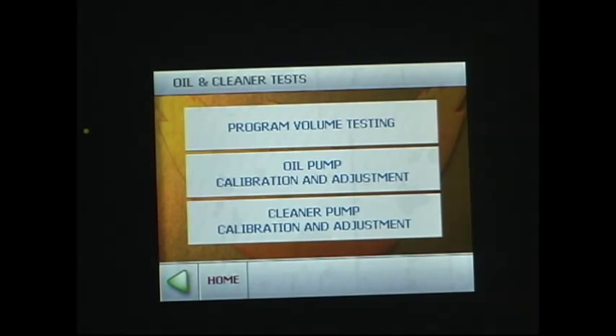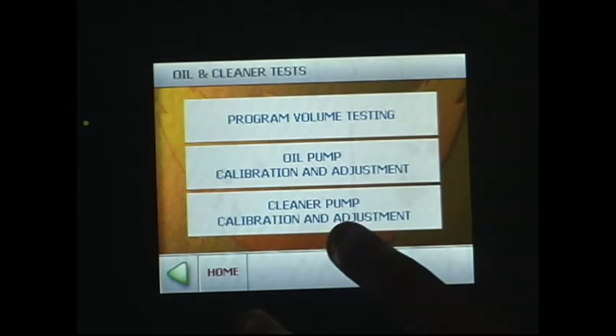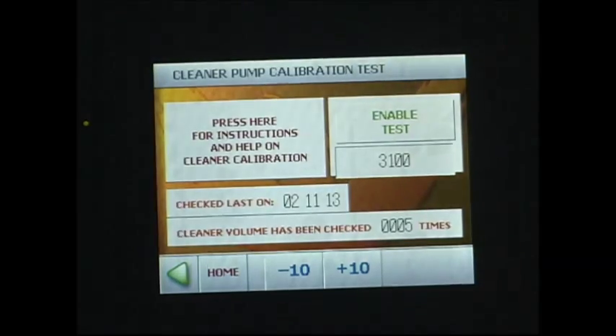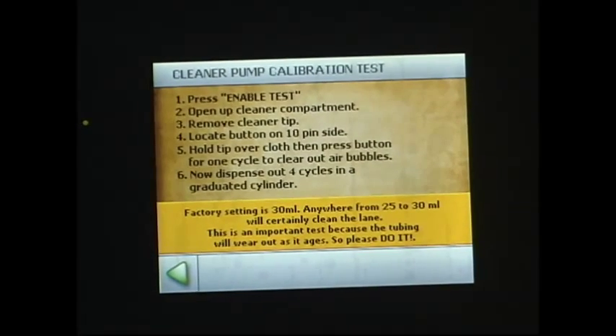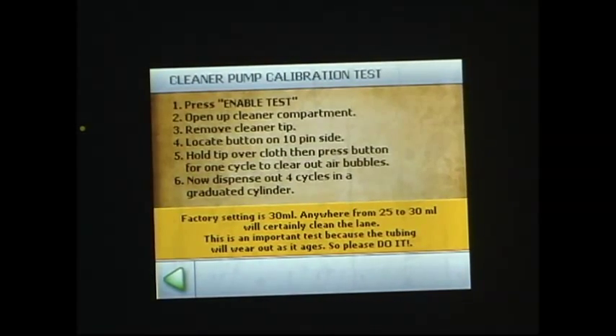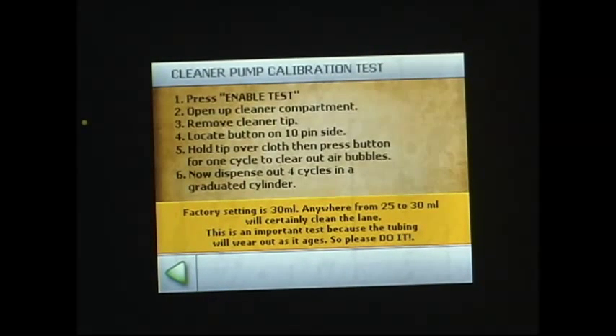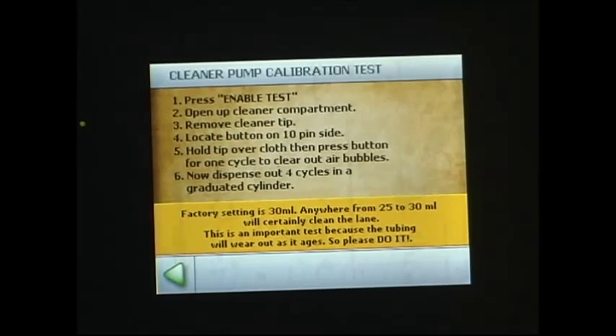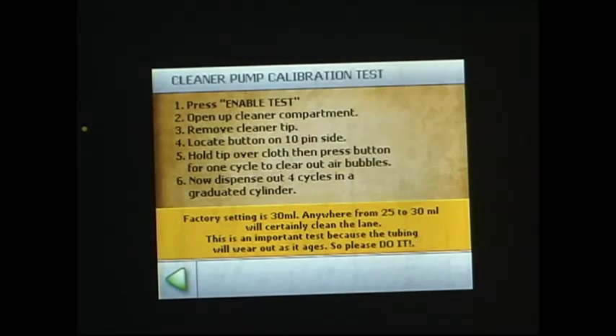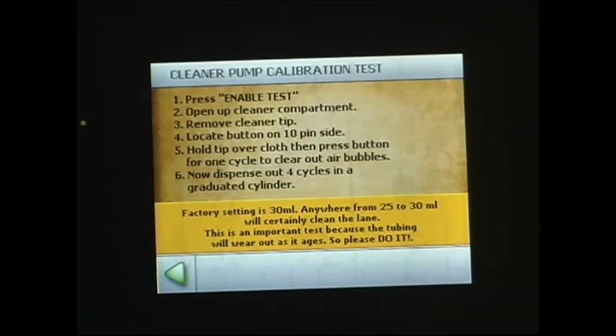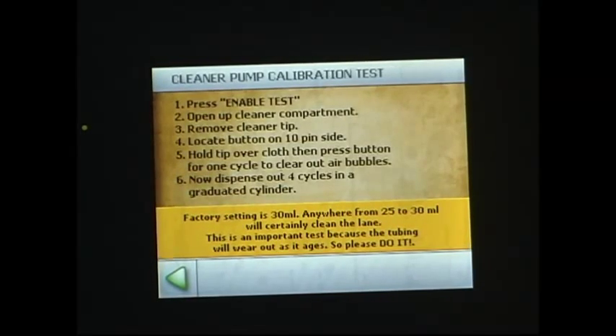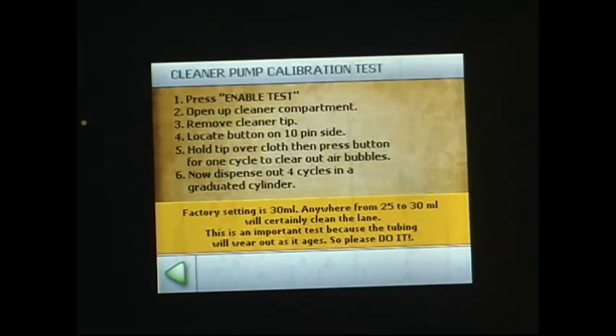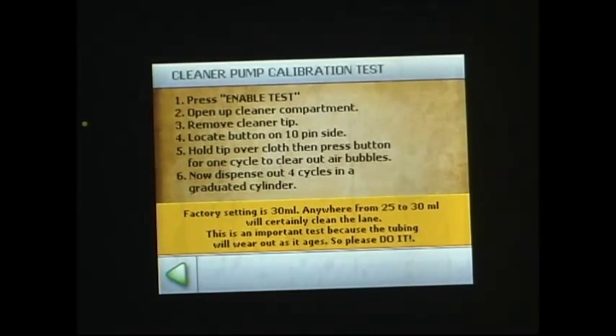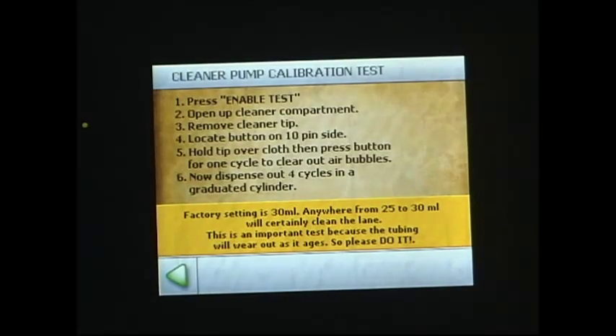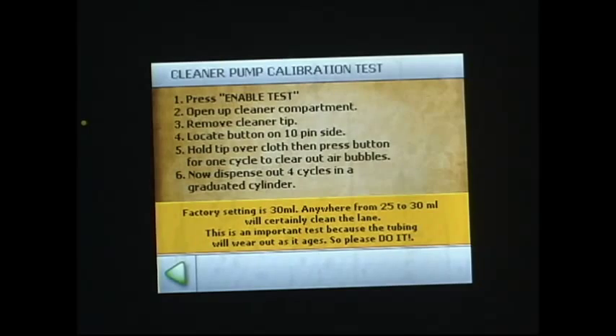Also, you'll want to double check the cleaner calibration as well. So we'll go into the cleaner pump calibration and adjustment. And then here, you can press here for the instructions and it gives you step by step. Step number 1, enable test. Open up the cleaner compartment. Remove the cleaner tip. Locate the button on the 10-pin side of your handle. Hold the tip over the cloth and press the button for 1 cycle to clear out any air bubbles. Now we're going to dispense 4 cycles in the graduated cylinder. And it's telling you here, factory setting is 30, but anywhere from 25 to 30 is enough to clean the lane.